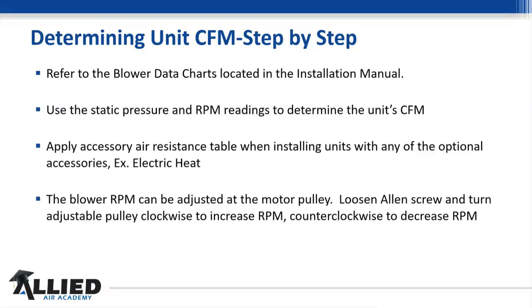So we're going to pull those charts out. We're going to have that book, and we're going to look at these charts and the installation manuals, and we're going to use the static pressure and the RPM to determine the unit's CFM. And then we're going to apply everything that we just talked about, and then we can make the blower adjustments from that point. And we'll talk about that.